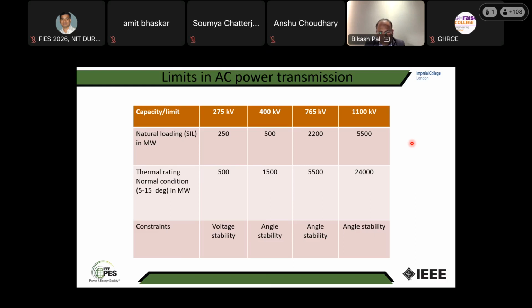And when the reactive power travels, that needs a voltage gradient. So that's a voltage issue. So the longer the line, up to this point there is a voltage stability limit. And beyond that, when the line is 200 miles, meaning 320 kilometers, and up, the voltage stability will not be the issue. The issue would be angle stability, and the loading will be far less than the surge impedance loading.